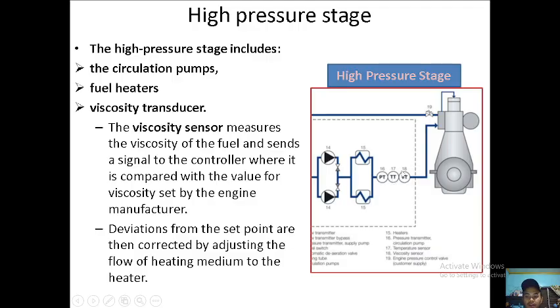So if the viscosity is very high, meaning the temperature is lacking and it needs more heating, the controller will send a signal to the heater to increase its heating capacity or heating input, depending on the deviations from the set point.